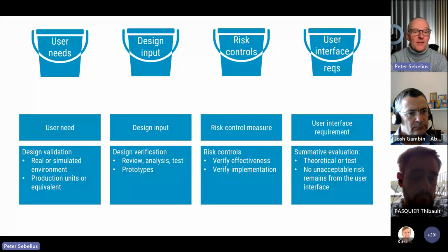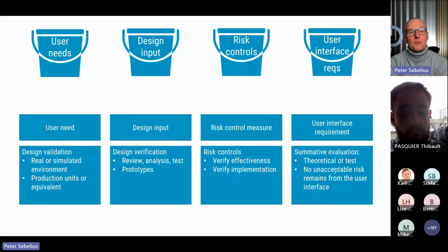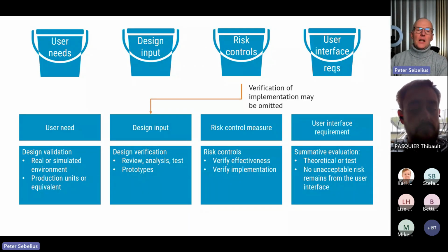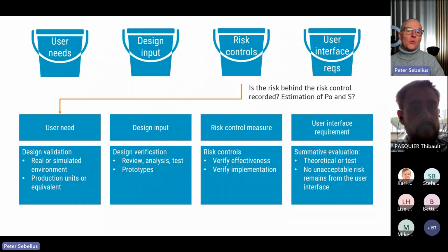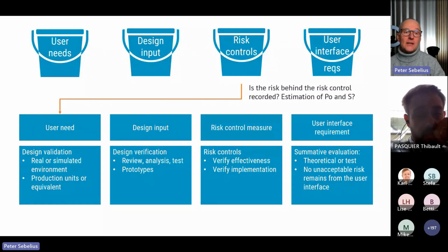And the purpose of the summative evaluation is to show that there are no unacceptable risks remaining from the user interface. This means that if you have a risk control measure and you try to route that through your design verification, there's nothing that ensures that you verify the implementation, right? Because there is no such question in your regular design verification. Or if you put in risk control measures as user needs, then there's likely to be some kind of risk behind it. I mean, that's the nature of a risk control.